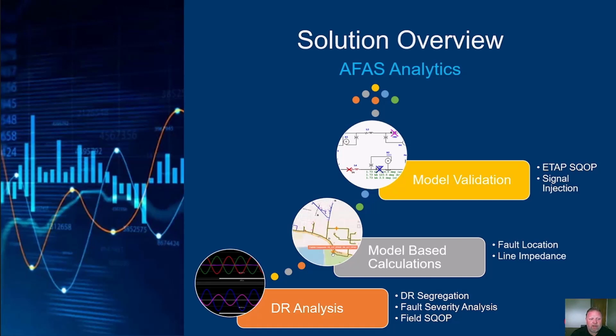Lastly, AFAS offers model validation by comparing the relay protection scheme as operated versus as designed by placing the fault into the ETAP model and providing the ETAP-generated sequence of operations, which can be compared against the field-generated sequence of operations. And signal injection allows users to play back recorded data in the protection model for further comparison. Overall, AFAS provides accurate and reliable fault analysis for transmission networks.